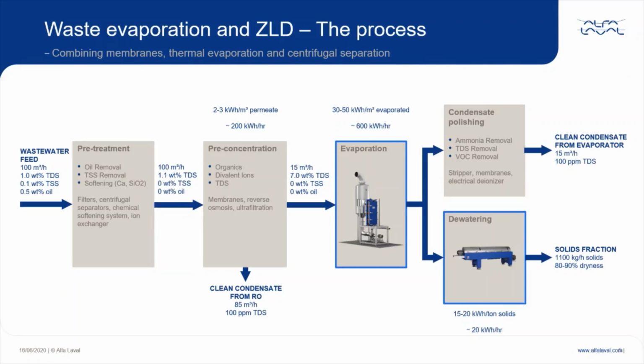Depending on the actual requirements in the recovered water, it might be necessary to also include a condensate polishing step to remove those contaminants. The working principle of the thermal evaporation system is removal of water by boiling, and this can be used for concentrating many different fluids containing both dissolved and suspended solids, but also for concentration of high boiling liquids. It should also be mentioned that in many cases it's not necessary, and in some cases it's not even possible, to reach the full zero liquid discharge with a dry solids product. There the evaporation process can still be used for volume reduction, minimizing the amount of waste that needs to be disposed of, and also recovering most of the water.